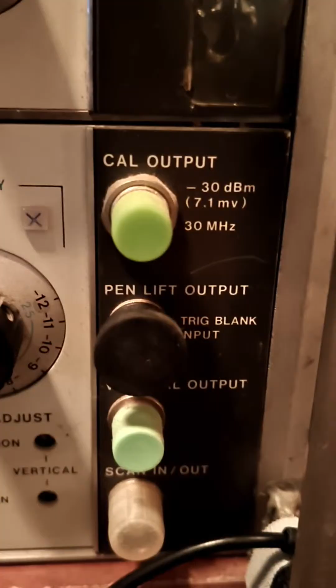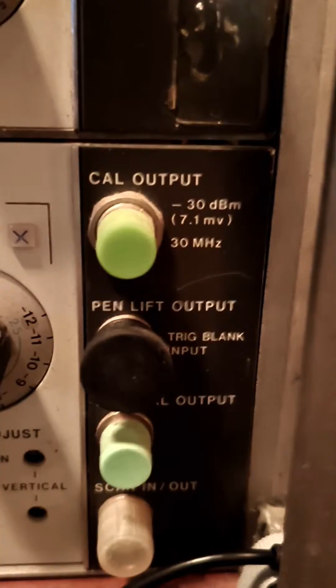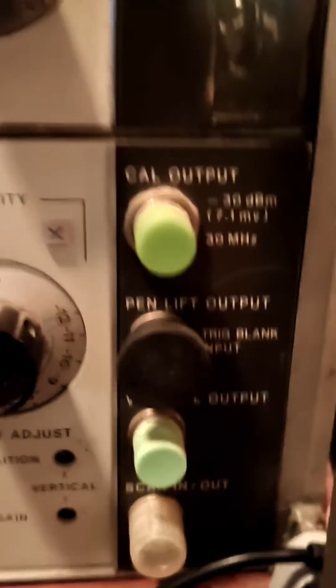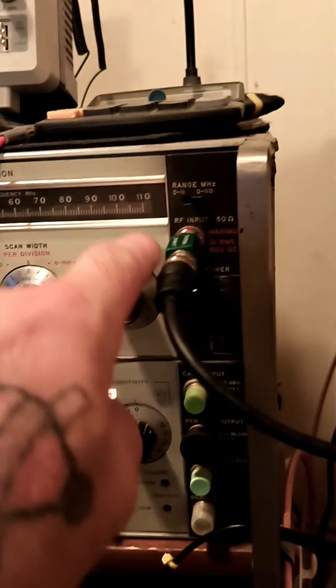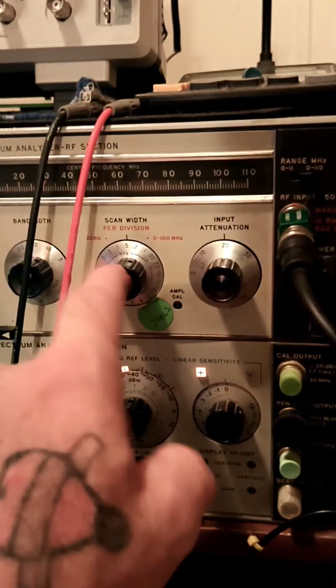It's got a built-in calibration output. So if you look at the bottom there, if I take my BNC cable and plug into that negative 30 dBm, that's going to give a 7.1 millivolt signal at 30 megahertz. And what that signal is for is to calibrate. If it wasn't calibrated right, you take that signal, put it into the front end of the machine, then you'd go to the right mode of operation. And what would happen is you would see the 30 megahertz signal. You'd see the second, third, fourth order of that signal, which is what that's going to show at 7.1 millivolts, negative 30 dBm.